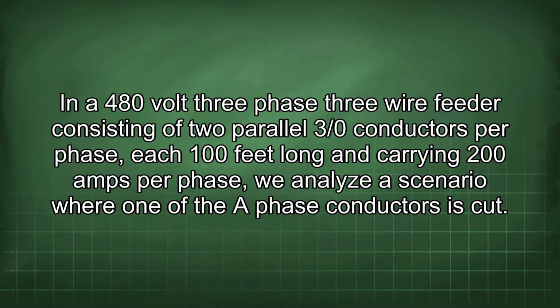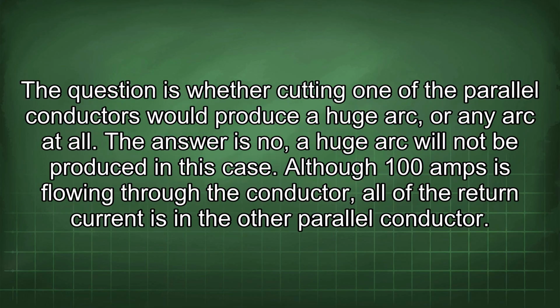In a 480-volt 3-phase 3-wire feeder consisting of two parallel 3/0 conductors per phase, each 100 feet long and carrying 200 amps per phase, we analyze a scenario where one of the phase conductors is cut. The question is whether cutting one of the parallel conductors would produce a huge arc, or any arc at all. The answer is no, a huge arc will not be produced in this case.